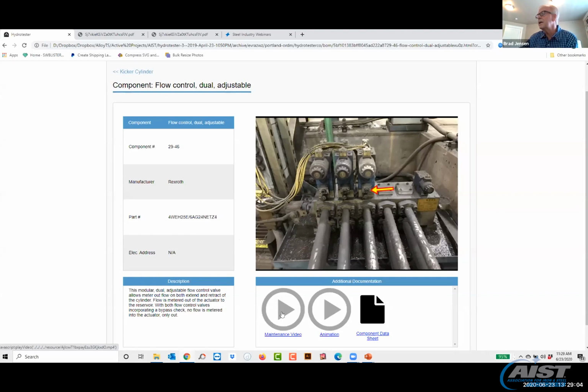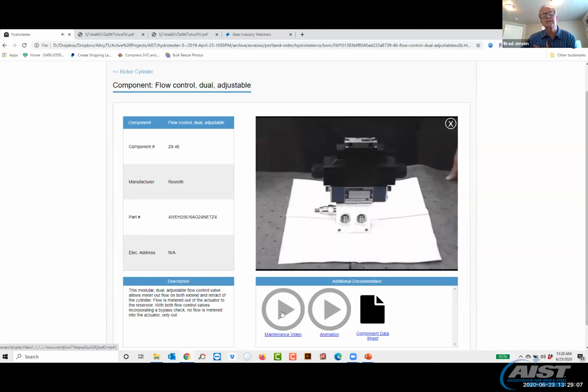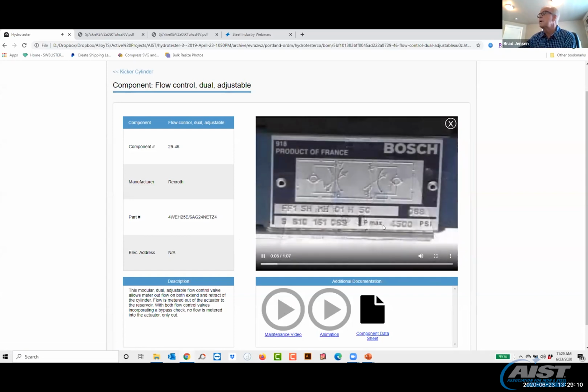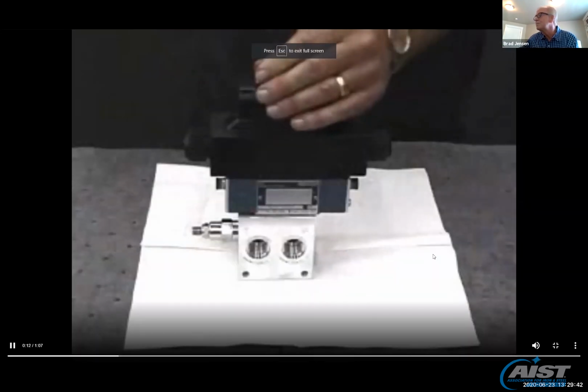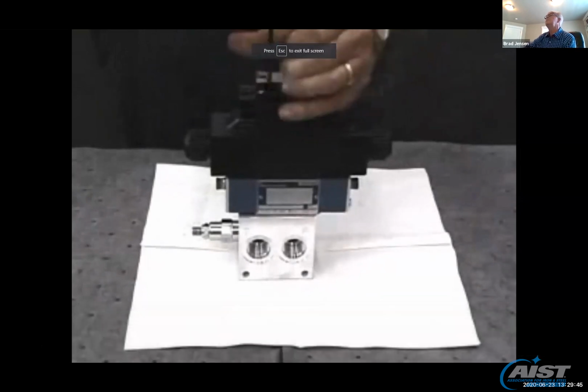I have here another piece of this data that exists out there. This shows the direction of fluid flow. This shows how you would pull that flow control valve out, and you can see by the symbology here that it's kind of critical which way it goes in. I can change from meter in to meter out just by rotating the valve. Well, for someone new that's never done that, it's nice to be able to put that reference there. First, by looking at the schematic symbol on the valve. Loosen the 4 hollow hex head cap screws and remove the D03 directional control valve.